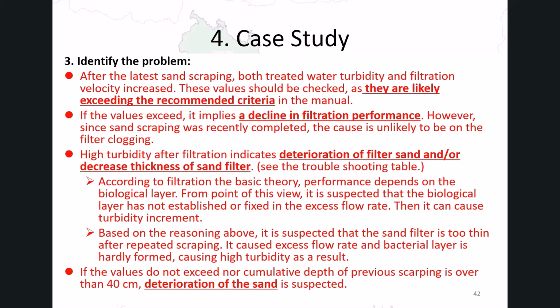Here, I am providing ideas about how to identify the problems. After the latest scraping, both turbidity and filtration velocity seem to have increased. But are they still within criteria or not? You have to confirm it. If they exceed, one thing is clear: the filter has deteriorated. One of the common causes that may deteriorate water quality is filter clogging. However, since scraping was recently performed, clogging is unlikely to be the cause.